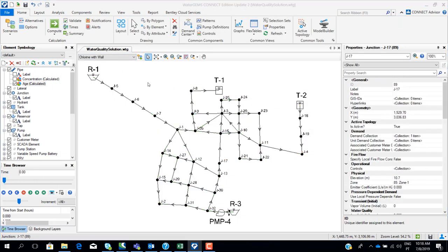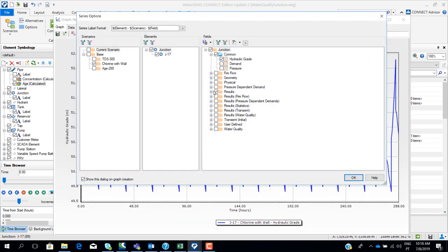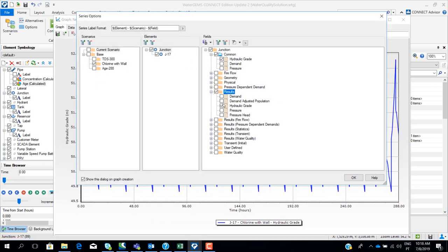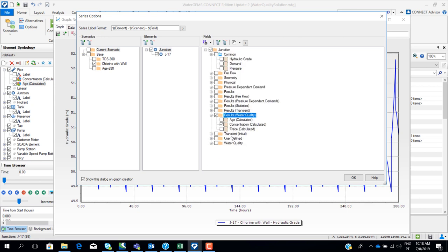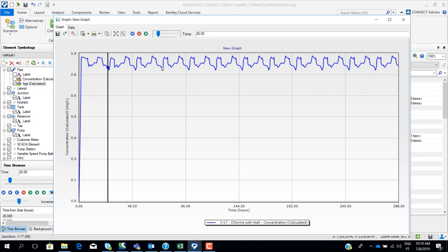We can also change the scenario to chlorine, right-click to open the graph, and instead of age select concentration. Here we have the concentration of chlorine at this node over time. It starts at zero and after some time reaches an equilibrium where chlorine is between 0.8 and 0.9 milligrams per liter at this node.